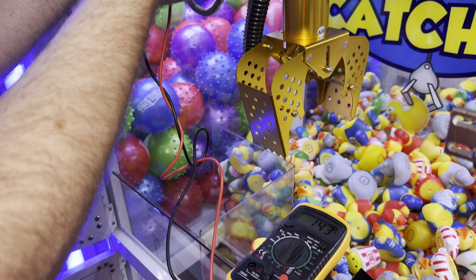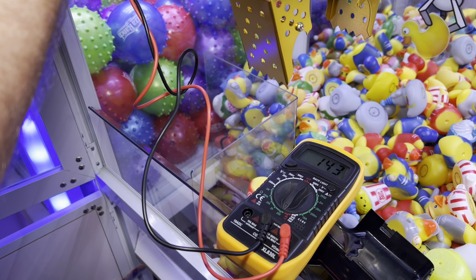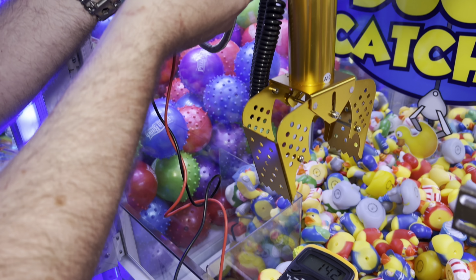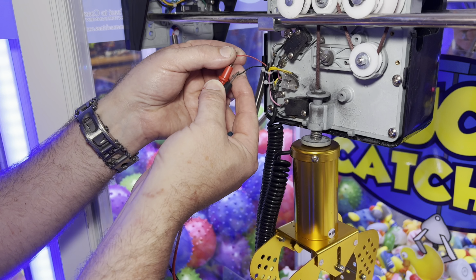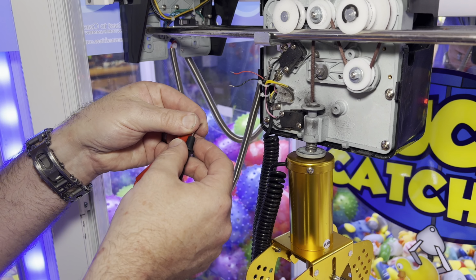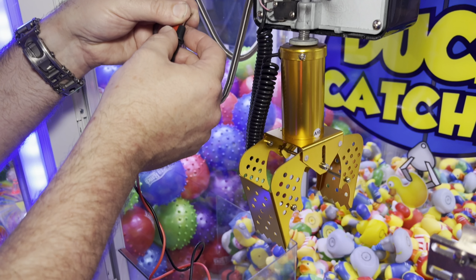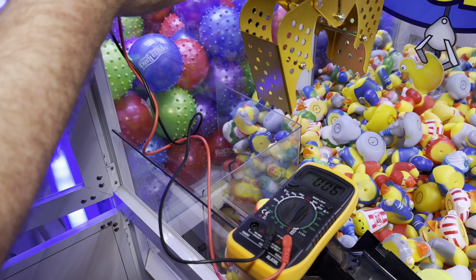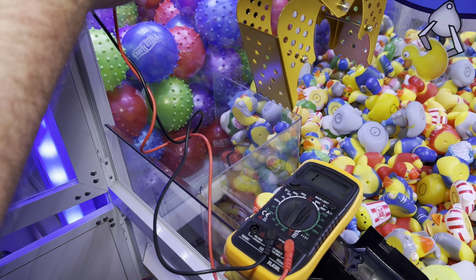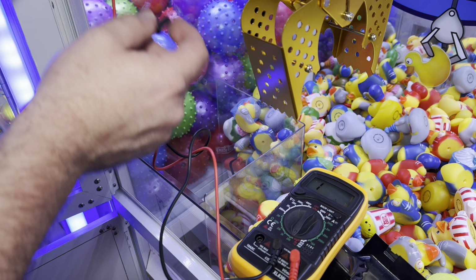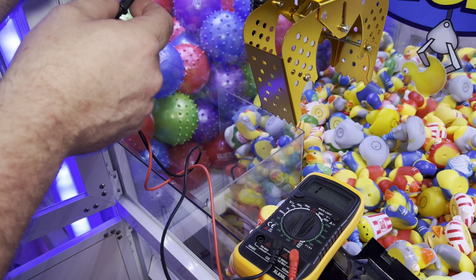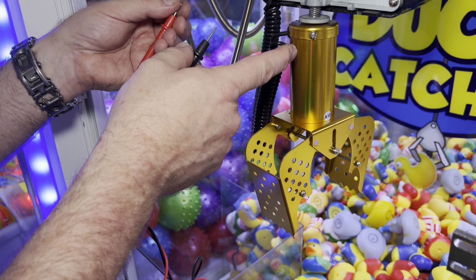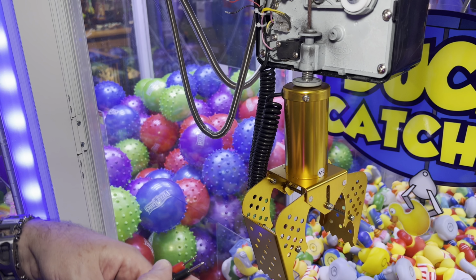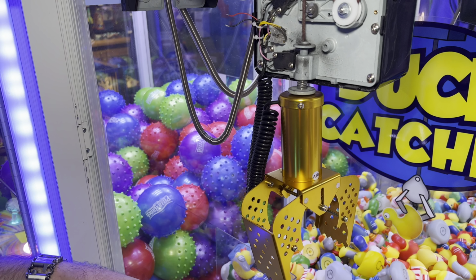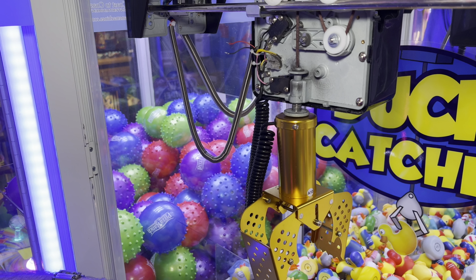If you look at the meter, we have 14 ohms. They usually test anywhere between 14 to 18. Those are all good values. If it says 0 or close to 0, that's a dead short. And if it doesn't say anything, that means that it's shorted open. If it has this 1 here, it means that it's over range, and that's infinite, that there's something burned out inside the coil. So 0 or a 1 means that the coil is not good and needs to be replaced.